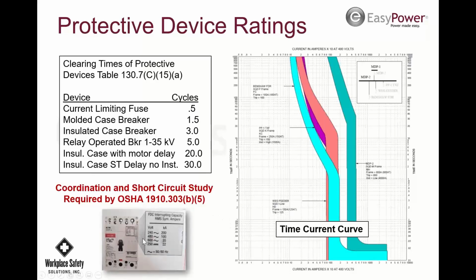Now here's a breaker. I've got breakers like this breaker. I don't know if you can see me or not, but I've got a breaker that's 10,000 amp rated. It's a Home Depot style breaker. That's the highest rating you're going to get, 10,000 amps, because your homes are not going to typically exceed 10,000 amps. This breaker that you see at 240 volts is good for 200,000 amps. At 480, it's good for 100,000 amps. These breakers you don't get at Home Depot. You have to go to an electrical supply store.